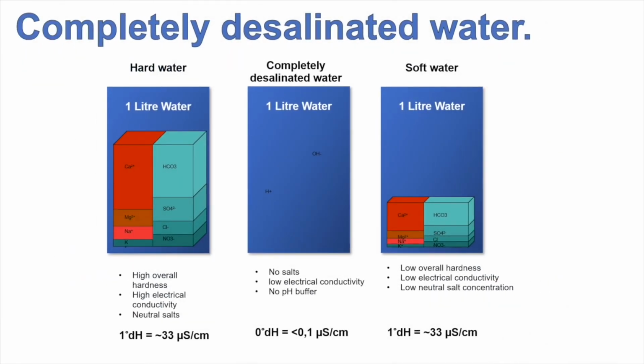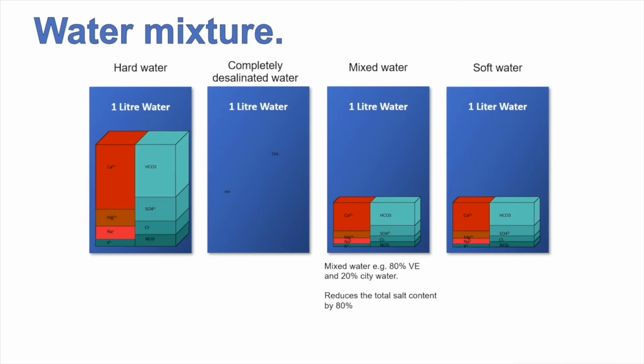A couple of charts here to show different levels of different water quality: hard water, completely demineralized water, and soft water. Got some water mixtures here. As I said in our video, you don't want 100% demineralized water. It needs to be above 10 microsiemens, but less than 100. Rule of thumb, you're looking at an 80-20% mixture.